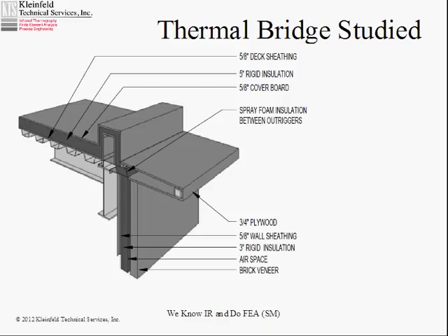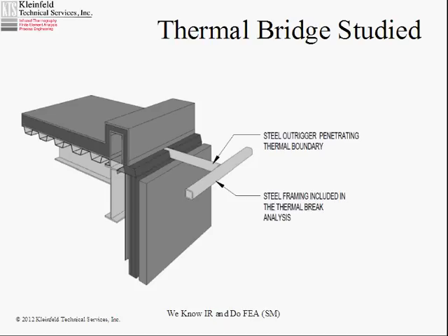This is the design that was studied — a portion of the building that has been sliced to show cross sections. What we have here is a visor, a roof, parapet wall, brick veneer, and rigid insulation. The thermal envelope of this building is the dark gray, and as you see it is continuous. However, there's a support for the visor, and if we remove the plywood — make it invisible — you can see the thermal bridge. This is tubular steel, three-inch square, with air inside, that is welded to the structural steel inside. It represents a direct thermal bridge through this building.